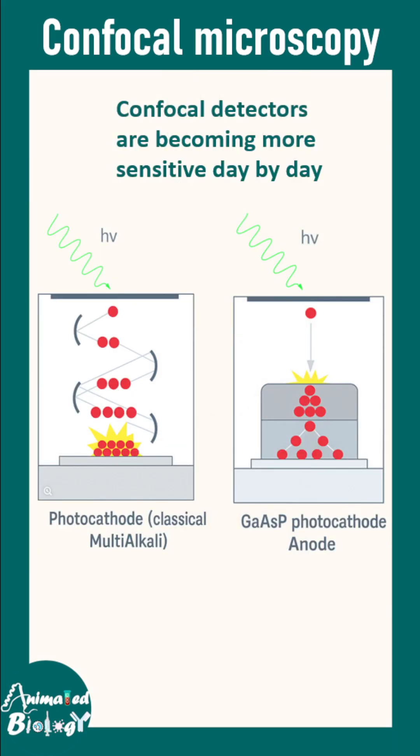These days confocal detectors are getting better and better. Instead of multi-alkali photocathodes, gallium arsenide phosphide photocathodes are now used, which are much more sensitive. The latest generations are silicon detectors. If you want to learn more, watch the full video.